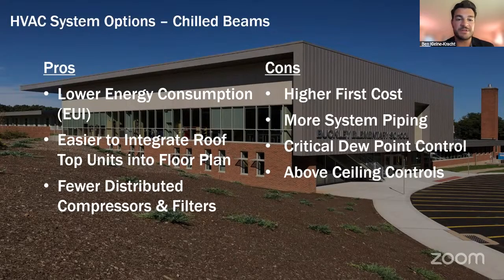Another con with the chilled beams is that they have really specific dew point requirements, and it'd be very difficult to get, let's say, operable windows in a good option like this, just because they are prone to condensation. But again, this is monitored, and we would design it so that it wouldn't do that. It is a well-known con of this option in this industry. And then there's just a little bit of controls above the ceiling with the valves at the terminal units themselves.